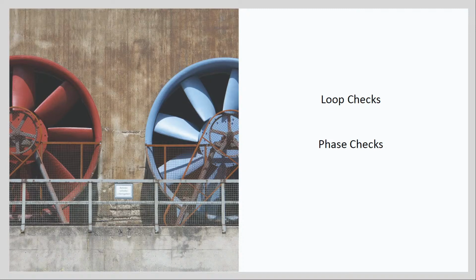So loop checks confirm the integrity of a control loop of the system. Sorry about that. Loop checks confirm the integrity of a control loop of the system from the HMI to the end device, including all cables and instruments. So a hot or operational loop check will confirm from the cubicle that the cabling is intact and that the field sensing device is properly installed, that the field device is properly calibrated, that the field device can successfully communicate with the HMI system, that ranges and set points are correct, and that information is correctly displayed on the HMI.